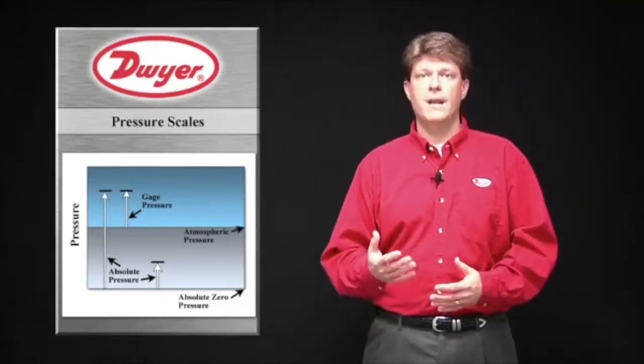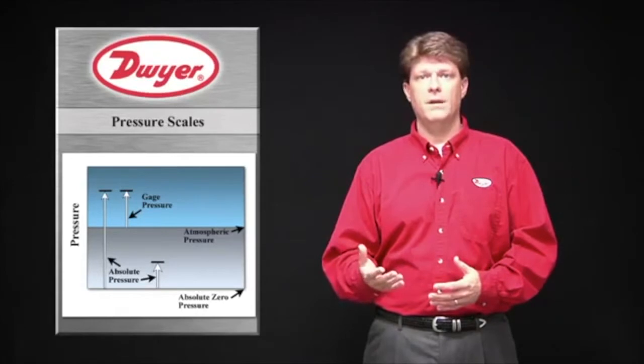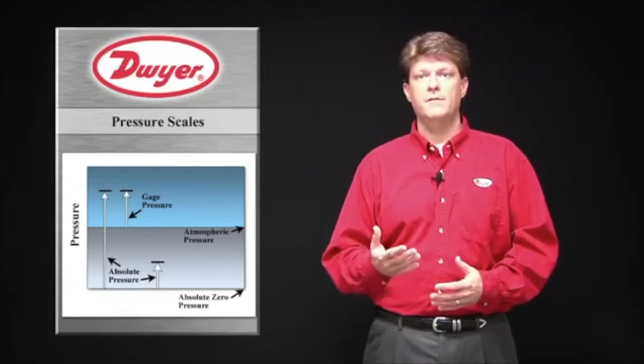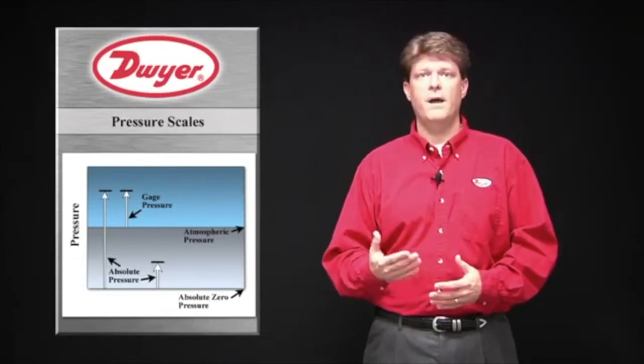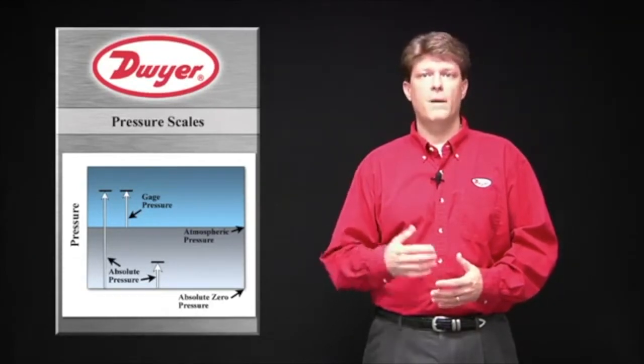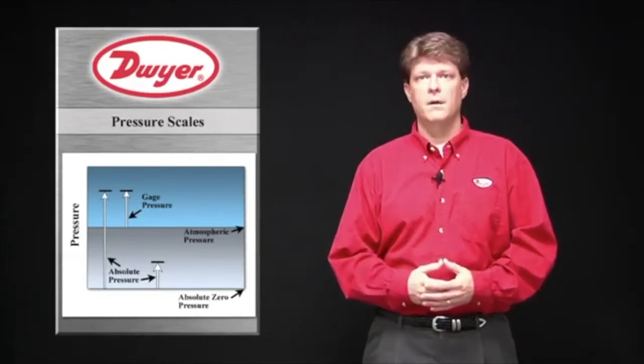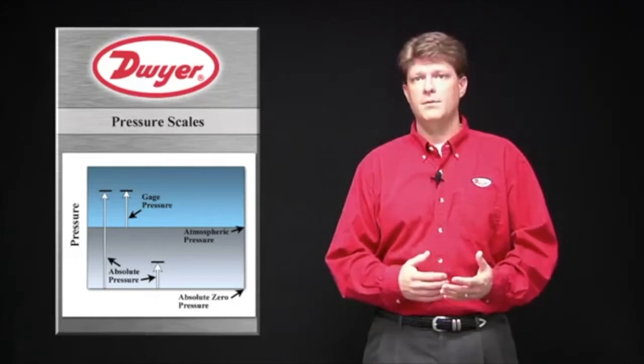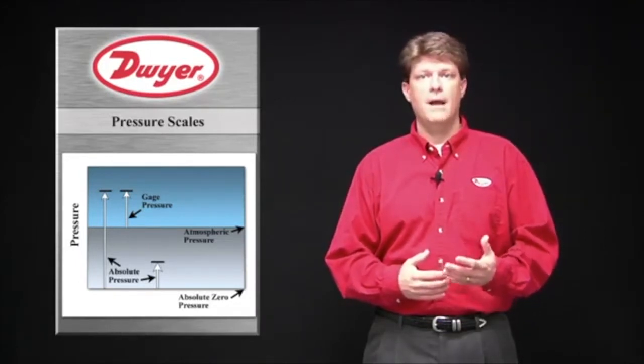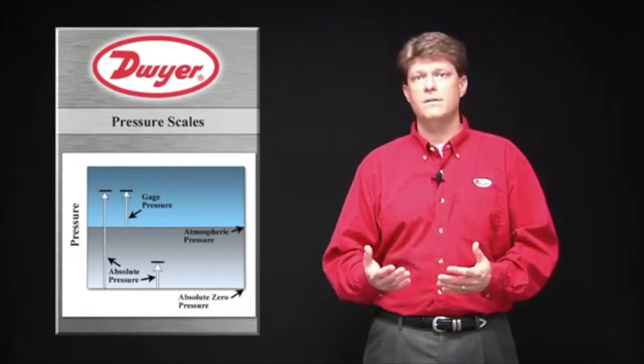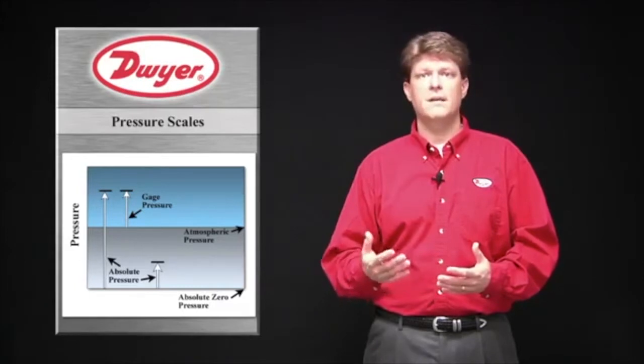Absolute pressure cannot be negative in reading and accounts for atmospheric pressure changes from altitude or weather patterns. Most absolute pressure reading instruments are calibrated and sealed so that the reference side of the sensor is held at a perfect vacuum.